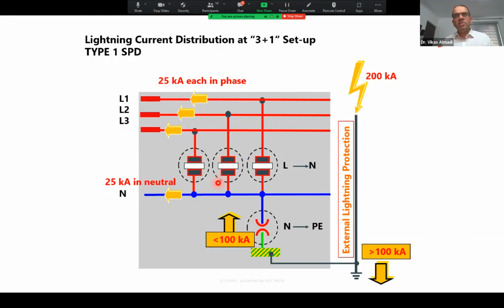But for industrial cases, there may be a requirement of more than one, depending upon the length of the cable. Because I mentioned the length of the cable creates oscillatory waves inside because of the di/dt case, and the distance between the point of installation of the SPD and the target equipment also matters. So that also gives us a clue whether we need another SPD or not.